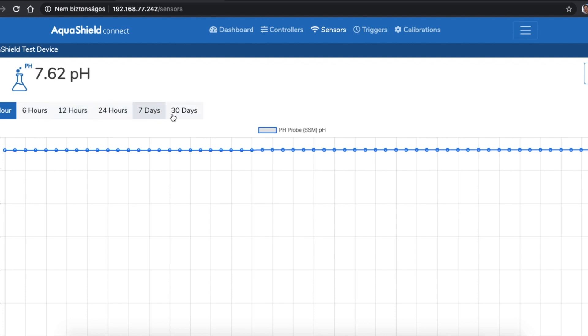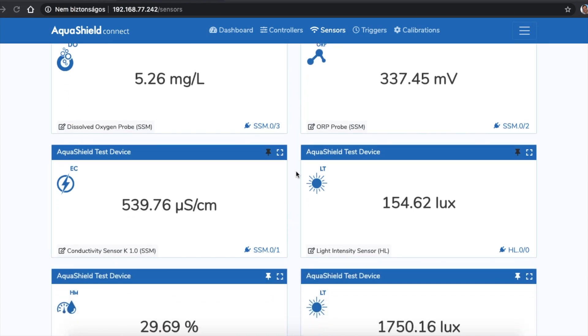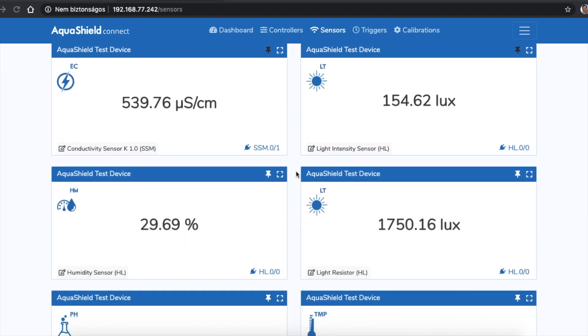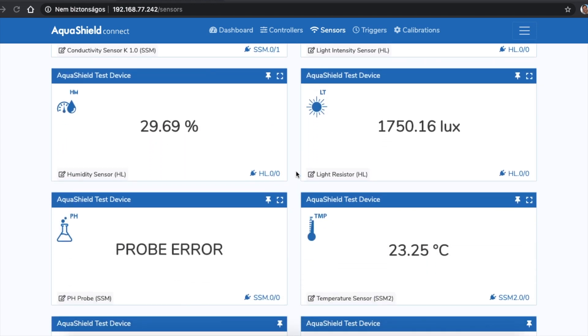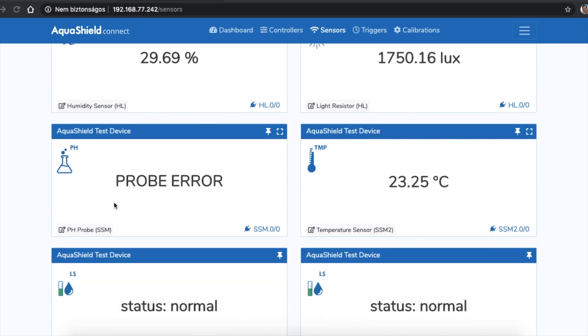From one hour to 30 days, you can choose what interval you are interested in. If there is no valid value on one of your sensor cards, it is possible that the probe is not connected properly or the sensor is broken. In this case, the card will indicate probe error or no CAN message.